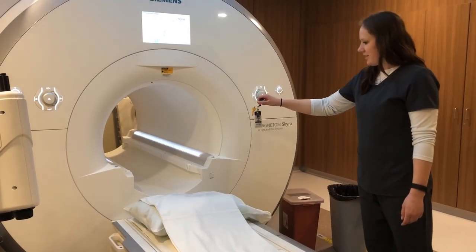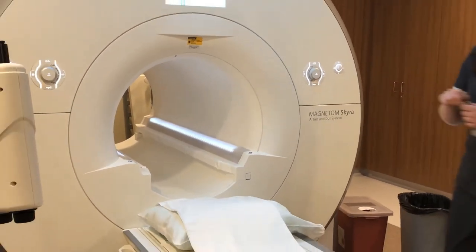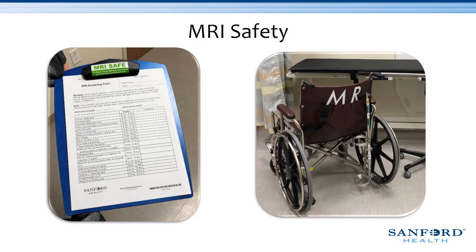This video demonstrates a metal badge holder attracted to the magnet within the MRI scanner. It is vital that patients and personnel be screened before entering the MRI suite. The screening form is in place to prevent potentially dangerous situations from occurring. Some items that are not allowed in the MRI scanner are hearing aids, dentures, insulin pumps, stethoscopes, phones, oxygen tanks, and more. Certain items have been made MRI safe and are labeled with an MRI safe sticker. Some patient care items made safe are MRI safe wheelchairs, headphones, and patient monitoring equipment.